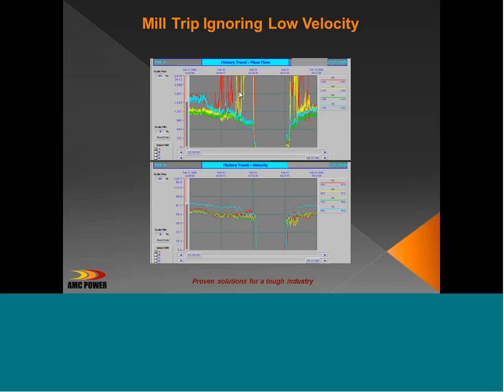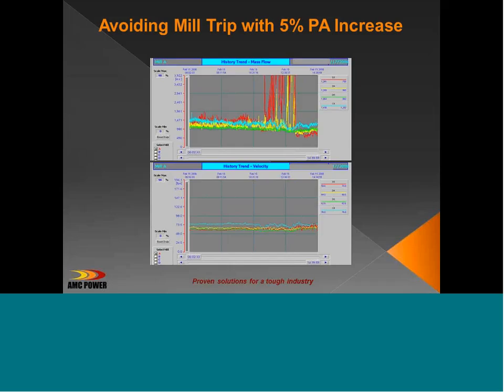So once the operator knew this, when it started to happen on another day, the operator chose to increase the primary air manually. So we saw again some coal settling out in his red pipe and the yellow pipe. So we increased his primary air, and you can see right around here the coal particle velocities start to increase from their low of right here where my cursor is.